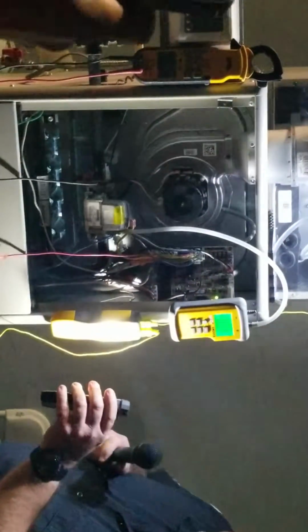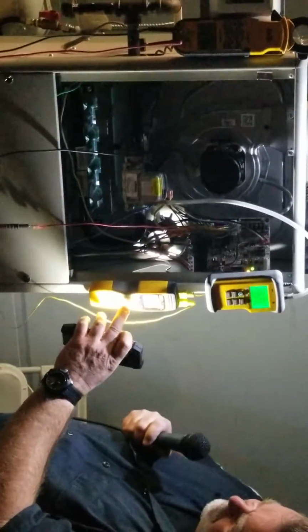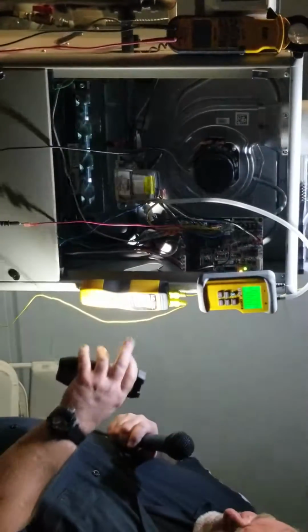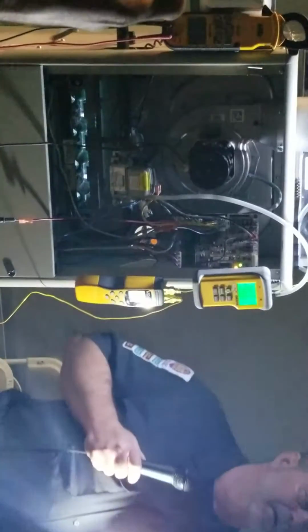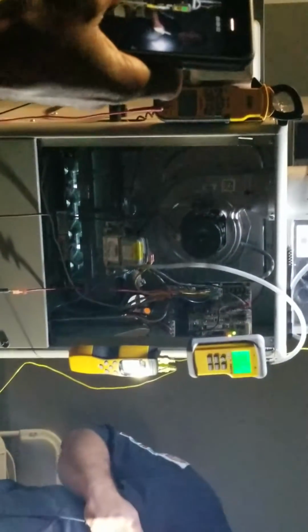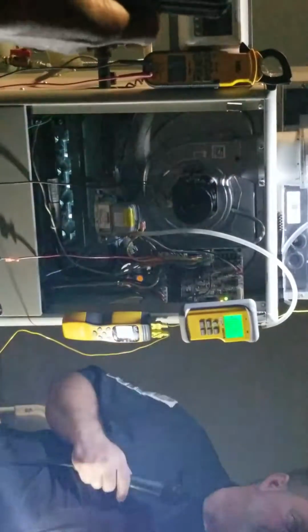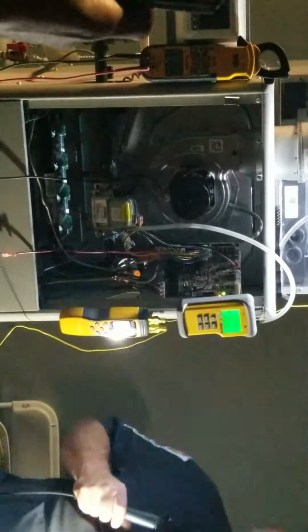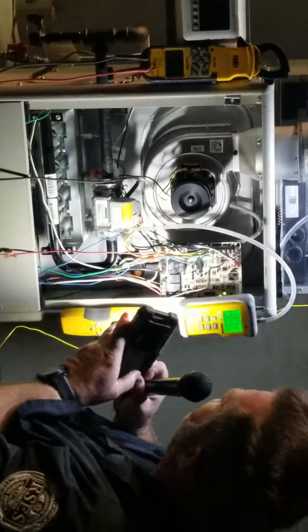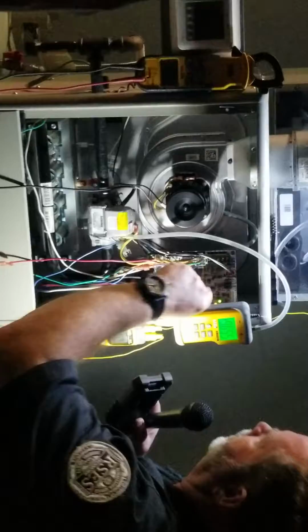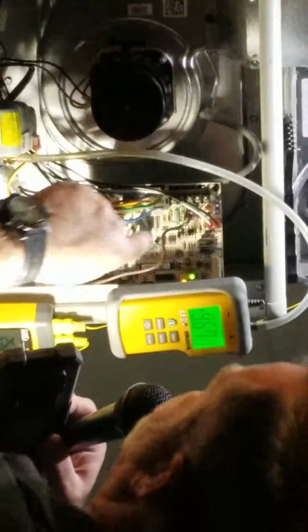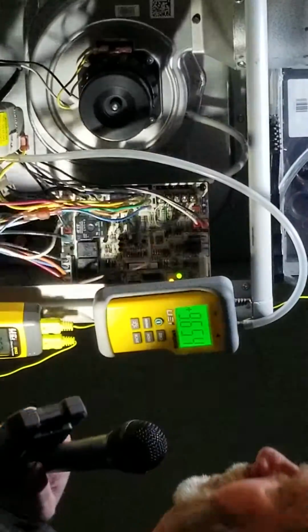And you can see what our temperature rise is. If you hit this mode, it'll tell you. This is giving me a 24.6 temperature rise right now. And as I leave this on longer, it'll get warmer and warmer. Plus, on this board, I can control my fan speed, and I can actually change the fan speed on this board very easily by doing this, while it's running.